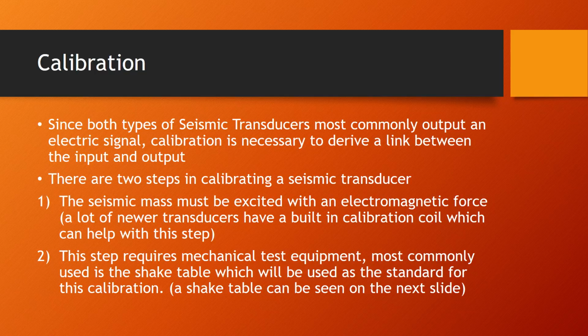There are two steps in calibrating all seismic transducers. The first step is exciting the seismic mass with an electromagnetic force. Many newer transducers now have a built-in calibration coil which helps with this step. The next step requires mechanical test equipment—often a shake table, which you'll see in the next slide, used as the standard for this calibration.